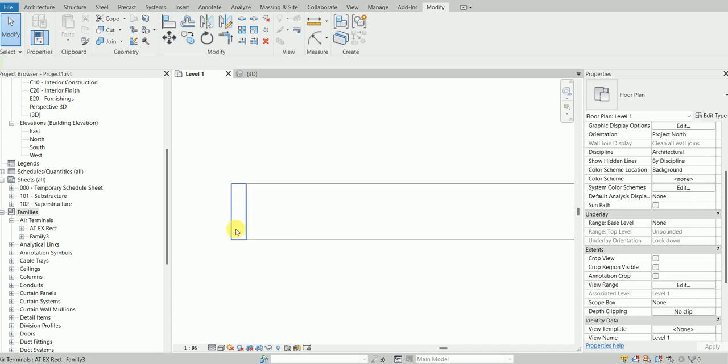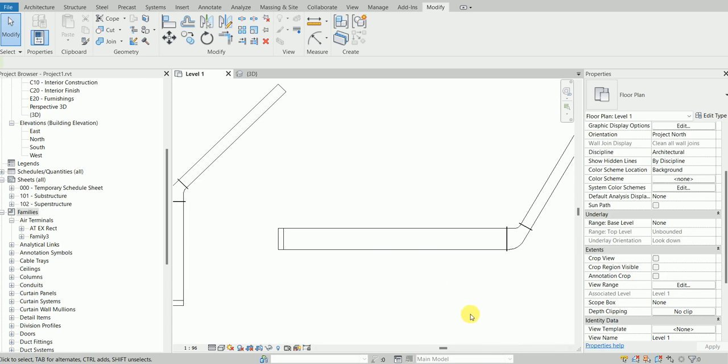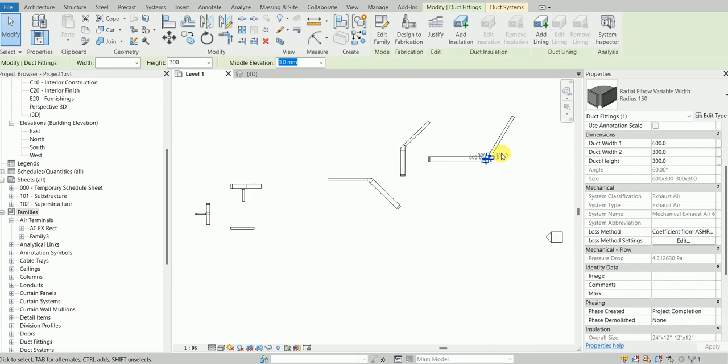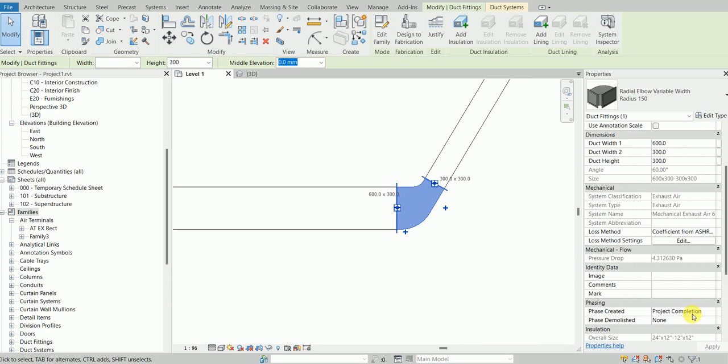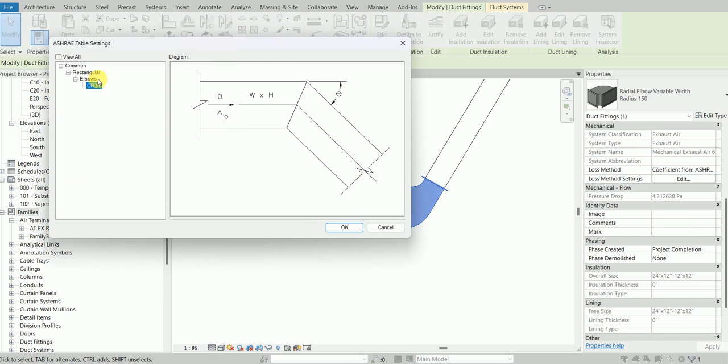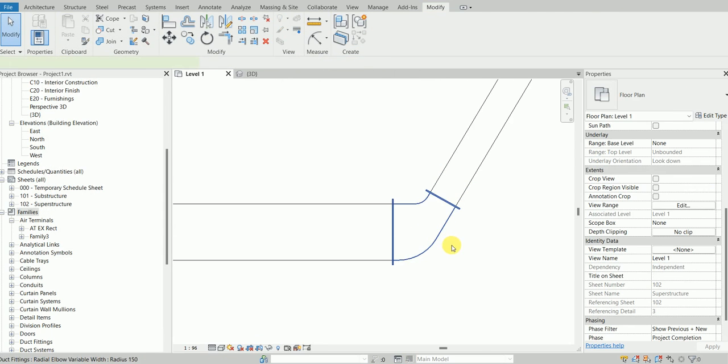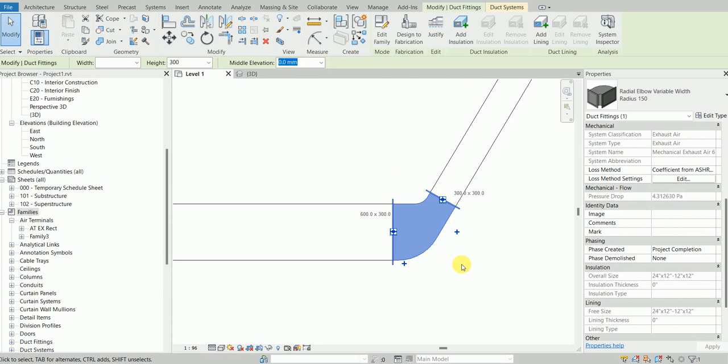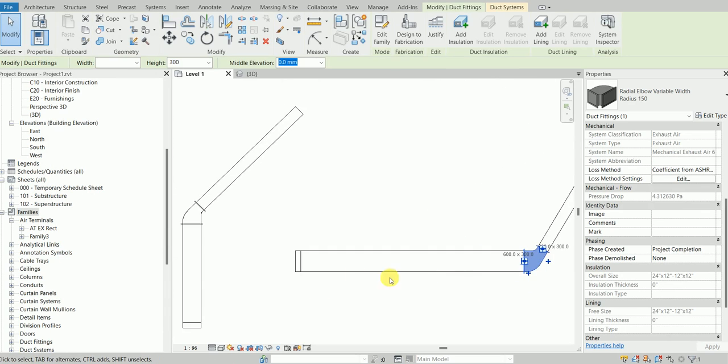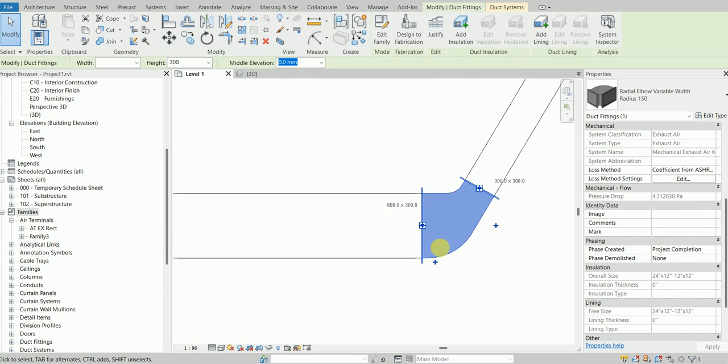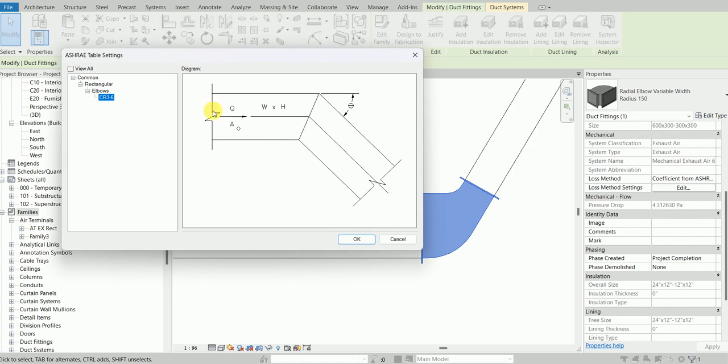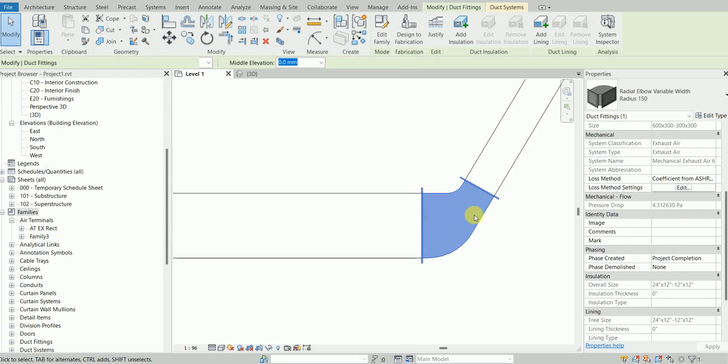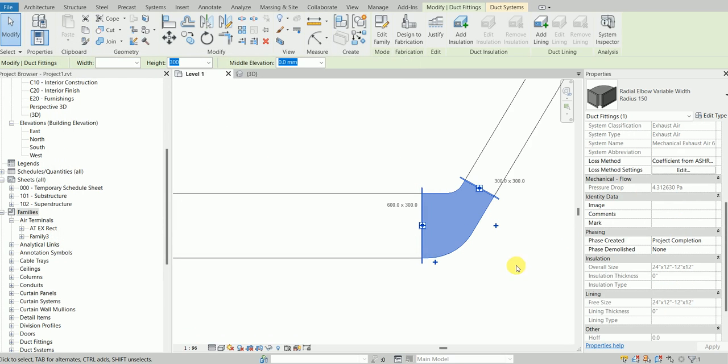Let's test this in the ASHRAE software. Let's first see what kind of ASHRAE fitting it picks up. This is the CR3-6 that it loads. That's the only kind of elbow which has this angle. Even though this elbow has the same width on both sides, it still does calculate the pressure drop.